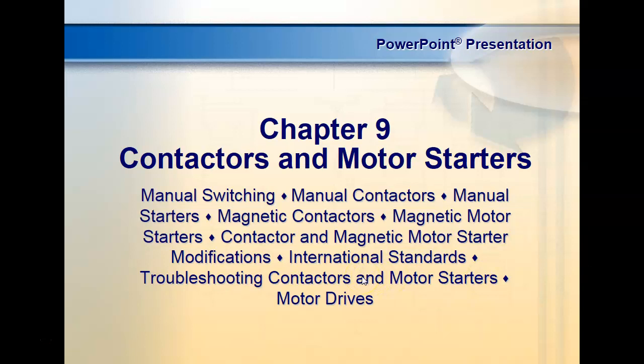So basically, we have three categories of relays in motor control. What are we? We've talked about this a couple times, guys. We have a control relay. Then we have what we call a contactor. Then we have, technically it's called a magnetic motor starter. Most people just call it a motor starter, because we have a manual motor starter, which we'll do a lab on. But a motor starter is some type of control device that has overload.